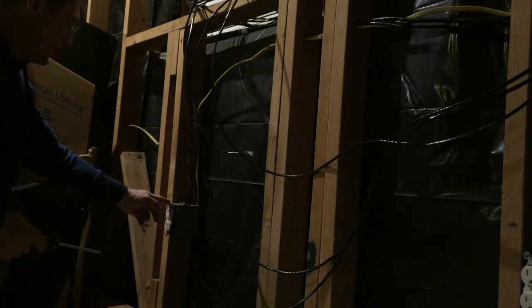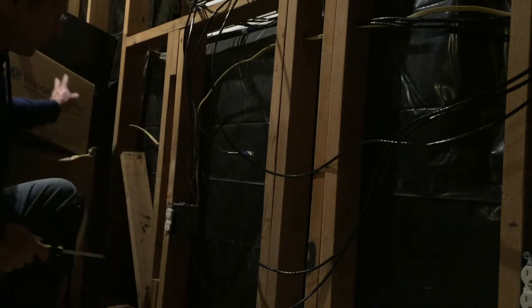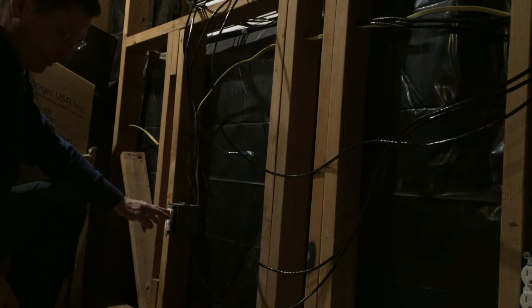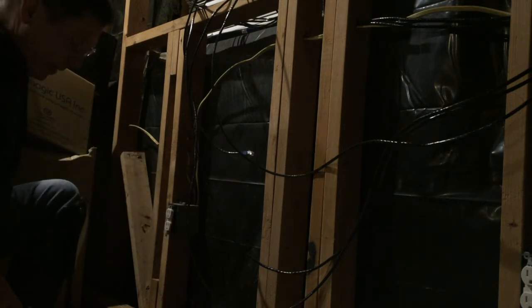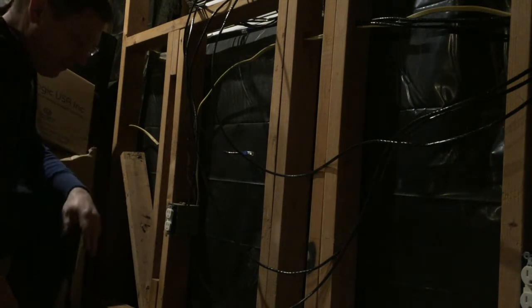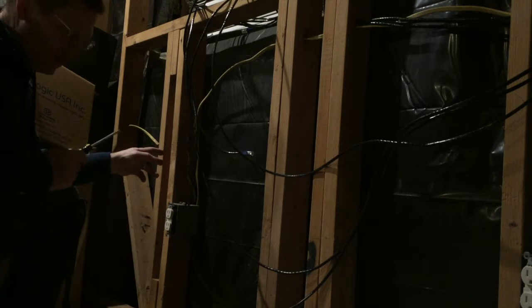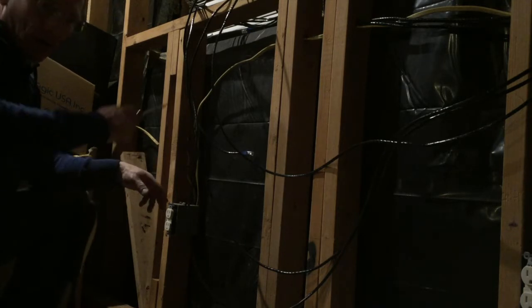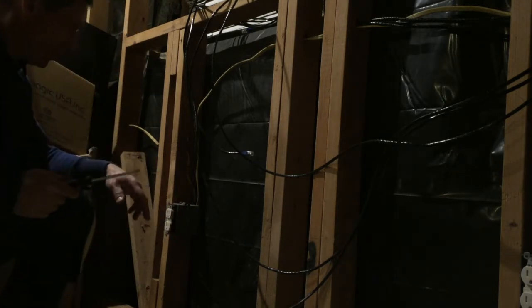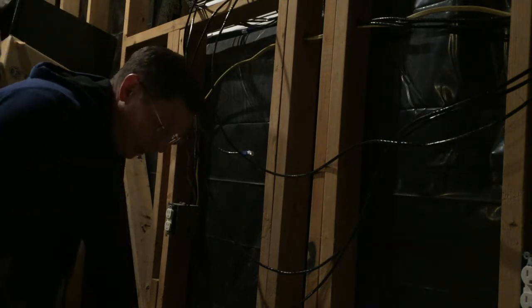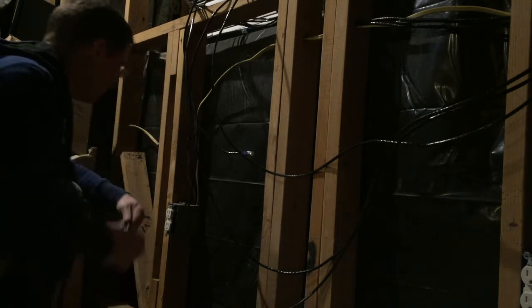Disconnect that one and leave the line side connected, and then I'll try to trip the breaker, and if it trips, then I know it's one of these 3 outlets that's shorting or spans of wire, and if it doesn't short, then I know it's one of these 3 wires and outlets that's shorting. And maybe I could save myself some time here.